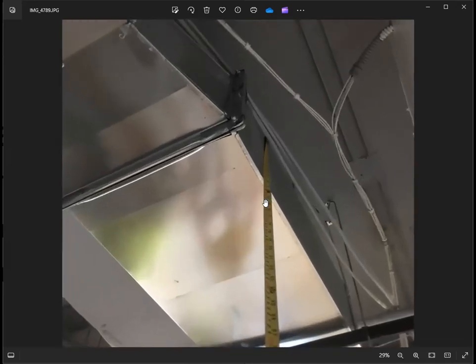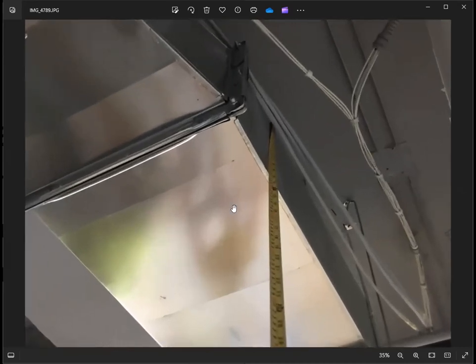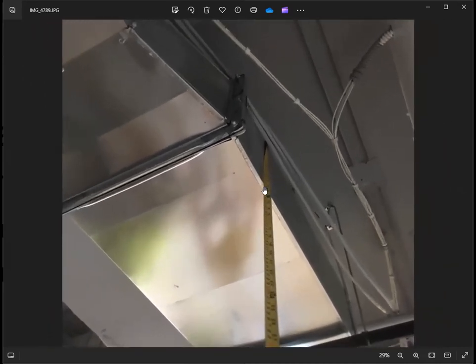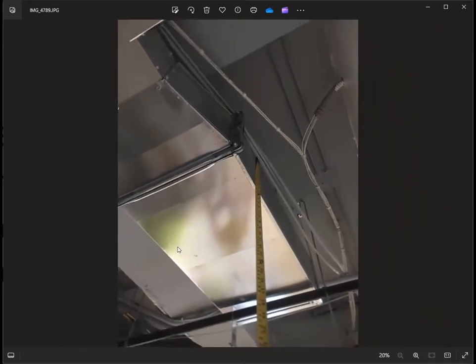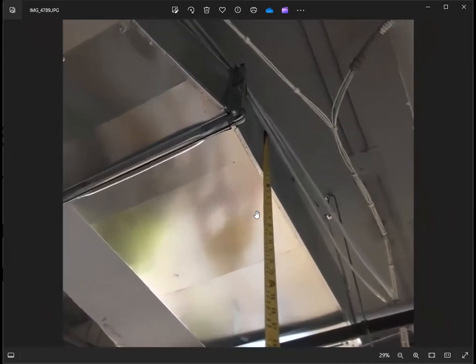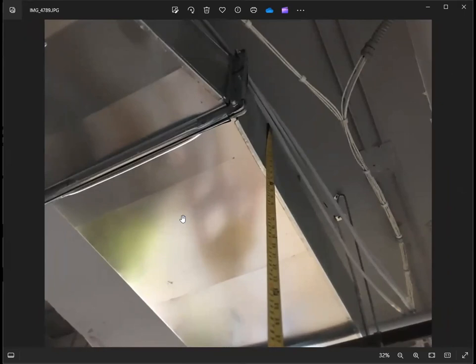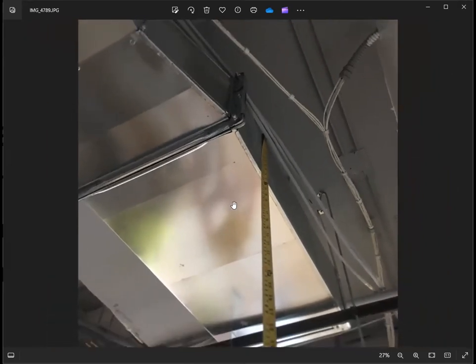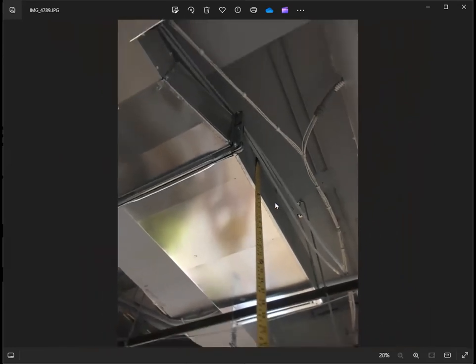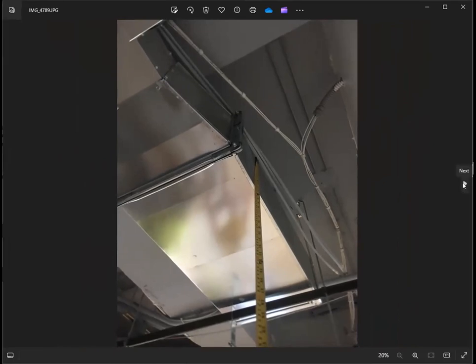And this is how I identify the ductwork size. So you need to also verify the ductwork size as per shop drawing. You could ask the contractor if they have a shop drawing, the approved one, approved by the engineer. This is how you measure it if it's already in the ceiling. This is the only way that you could identify the size, and you need to identify also the gauge, the thickness of the ductwork material.